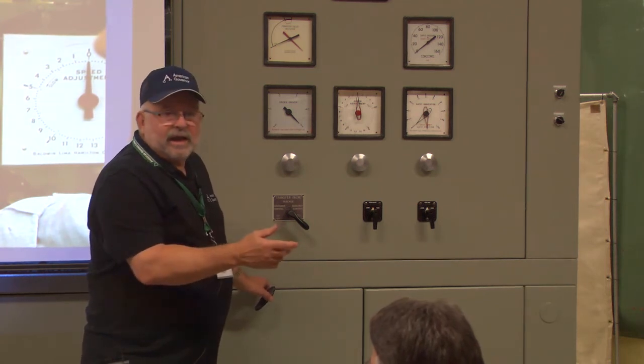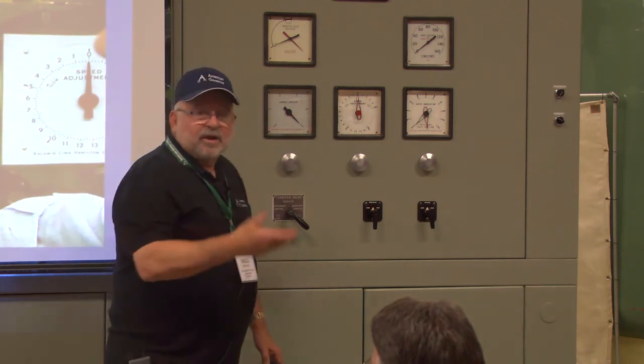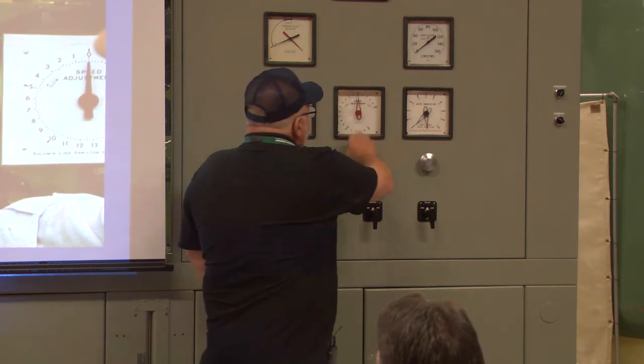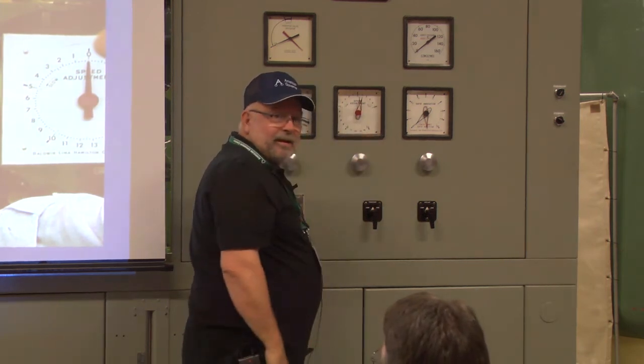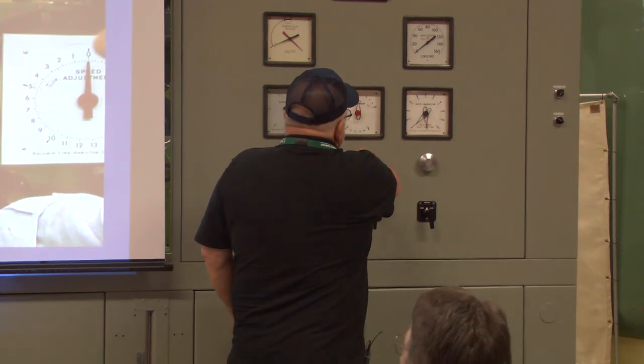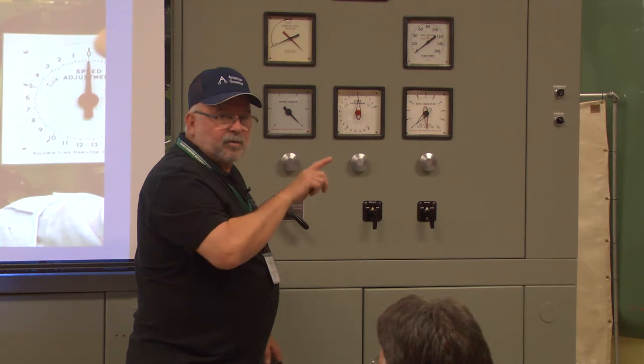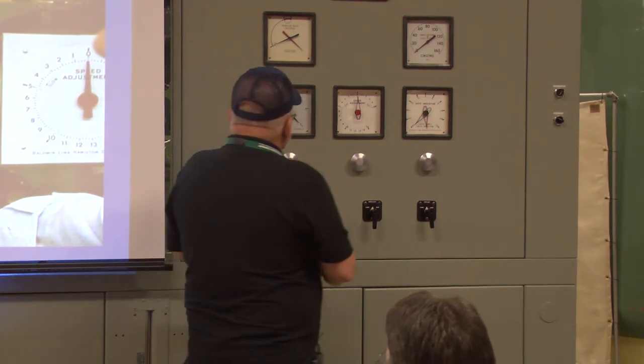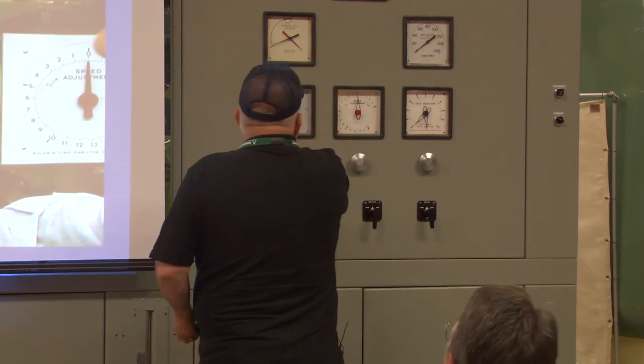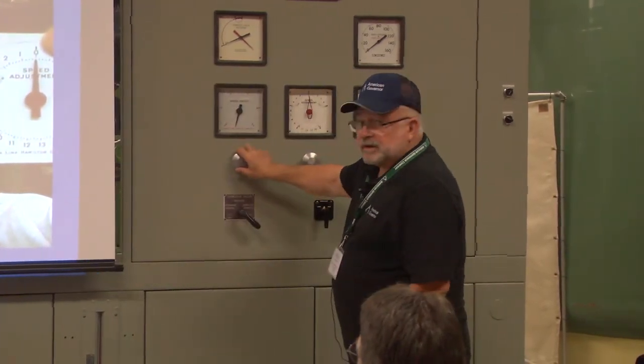If you do it online, you're going to load megawatts on. So an operator is going to want to know what you want them to do. I want you to make one complete turn with that, and then give it three minutes or so. And then you can go back the other way. The important thing is back and forth, and the zero affects the span every time. You look at the span on this.